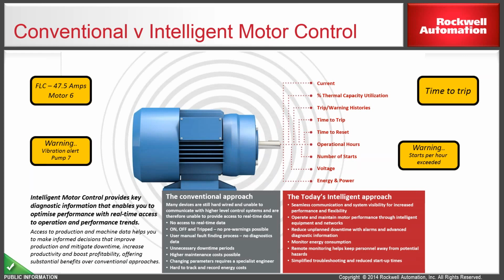What parameters does it give you about the motor? It gives you the current, the thermal capacity utilization of the motor, trip and warning histories, how many trips and warnings occurred, time to trip, time to reset, cause of trip, how much time the motor has run, number of starts, voltage, and how much energy it has consumed. Overall, it gives very significant information about everything happening inside the running motor.